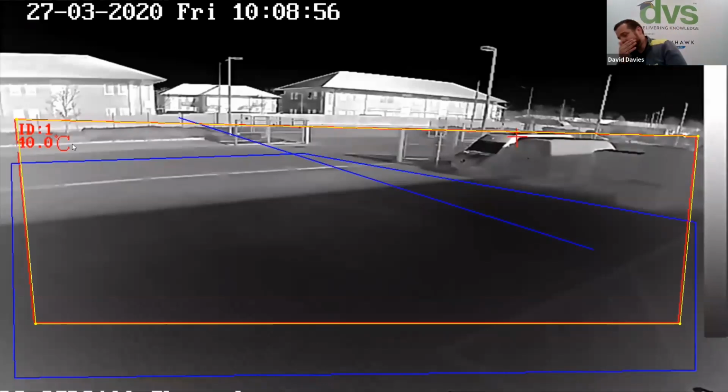Sorry, it's not that temperature. Obviously glass, they all reflect things differently. That's covering a lot of stuff there. And again, based on this being plus or minus 8 degrees, it's not going to be as accurate as you think. What you also have to remember is that the van is made of metal. The sun is on that van now, and it's black matte paint on there. It does get quite warm to the touch. So whilst it's not going to be 40 degrees if I actually touched it or put a thermometer on it, it would appear a lot warmer than the ambient temperature outside. So just things you have to be aware of, that you could get readings that don't actually make sense. But that would be one of them.